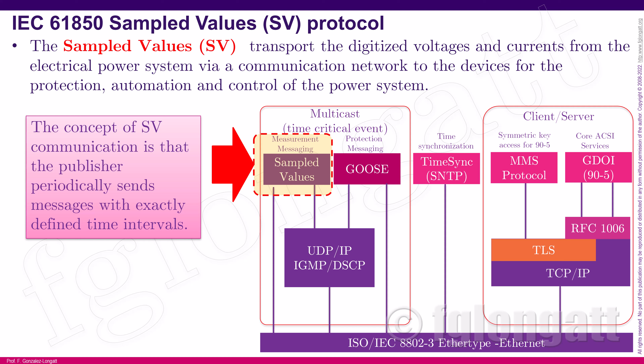I'll go to one relevant for the person who asked about communication protocols. Power systems have been populated with communication mechanisms for many years, creating several communication and data protocols. One of them is IEC 61850, a standard for the architecture and communication of digital substations. Inside that protocol we have several layers of data flows and data streams, from the very slow MMS to the very fast sample values.